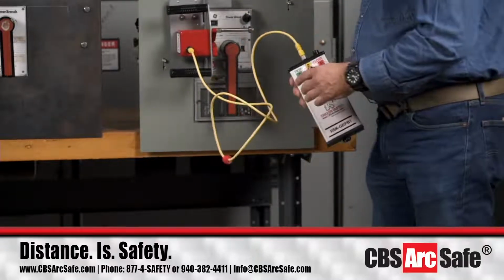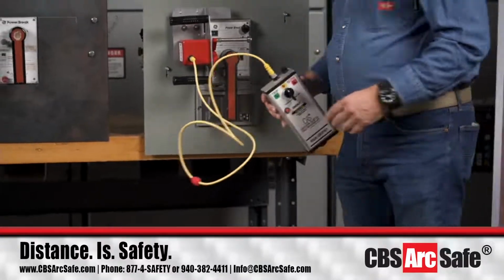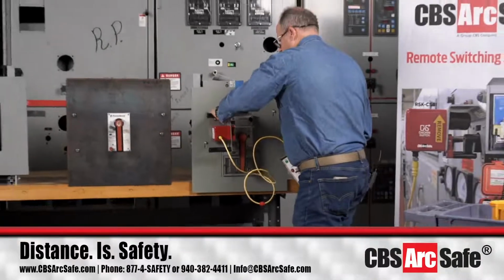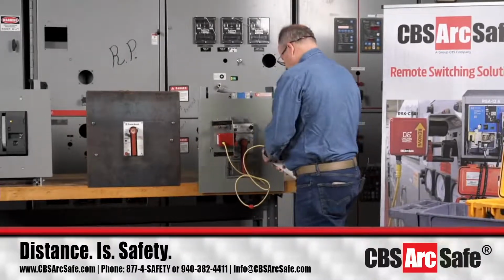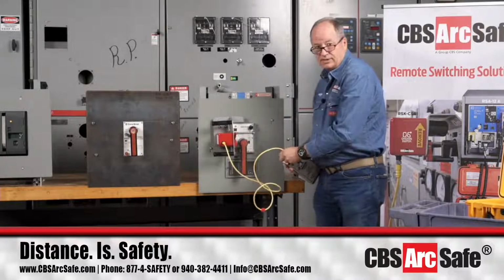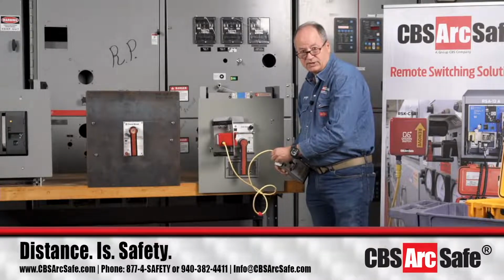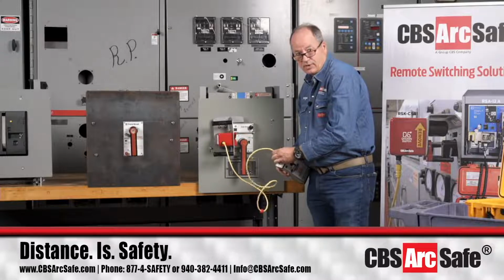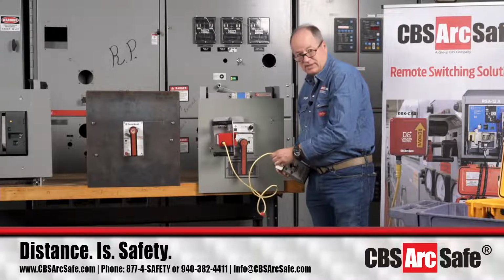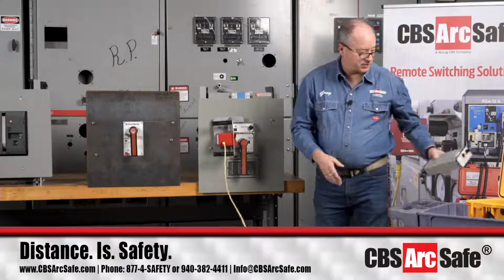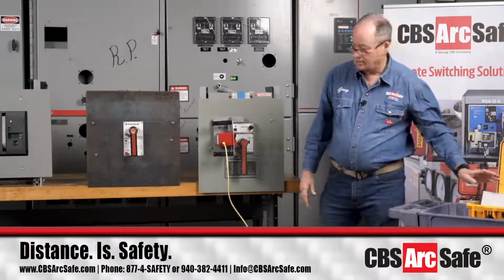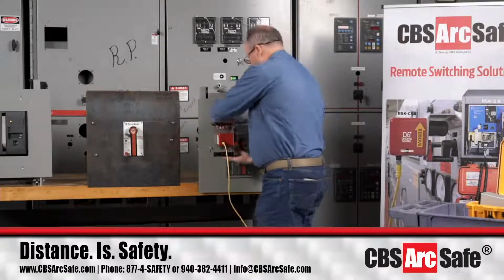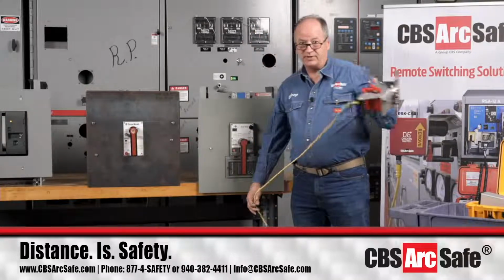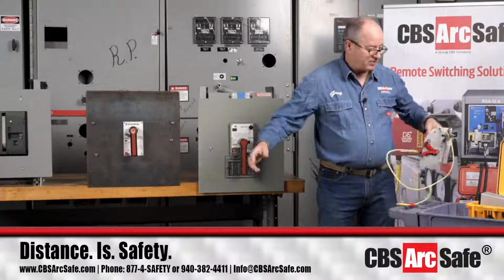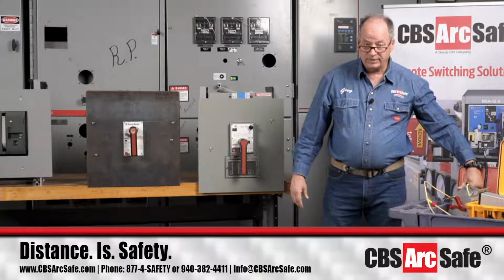Always know what your arc flash hazard boundary is, so that when you're doing this, you can stay outside of the boundary. I can't tell you the number of times, whether I've done this internationally or domestically, the first time people see an RSA operate or remotely racking something, they like to stand there in front of the switch. And you're like going, no. There's a reason you got this big placard here that says 10 feet away. Step outside of the boundary to operate the equipment.